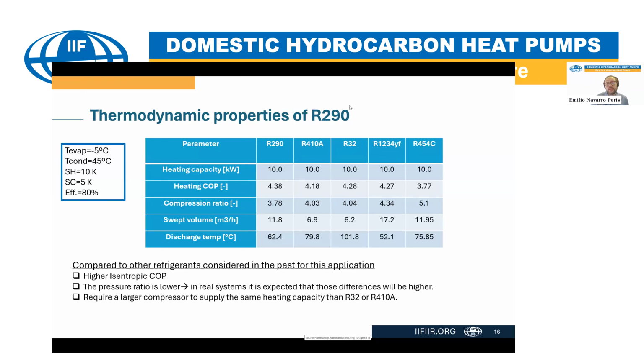Looking at the swept volume of the compressor, or the size of the compressor, we see that compared to R32 or R410A, we need to increase the size of the compressor quite a lot for propane to supply the same capacity. But if we compare propane with other alternatives like R1234YF or R454C, the compressor size is not a disadvantage in those cases.